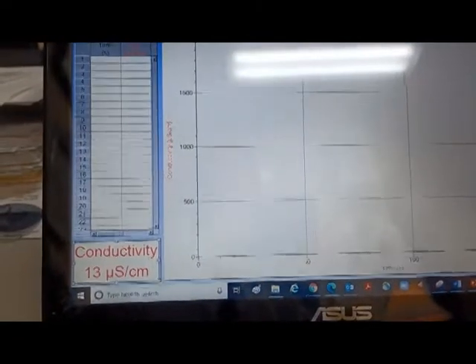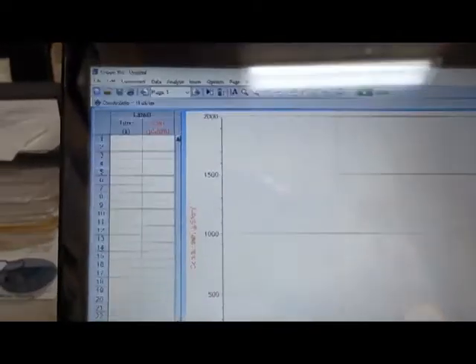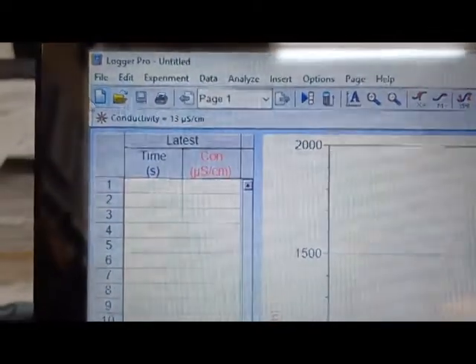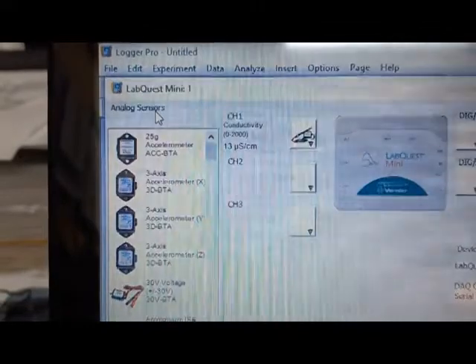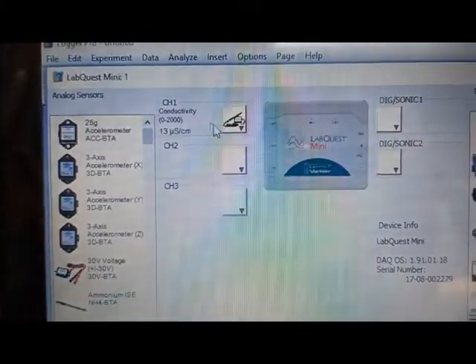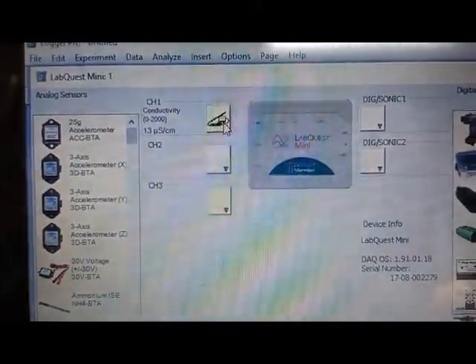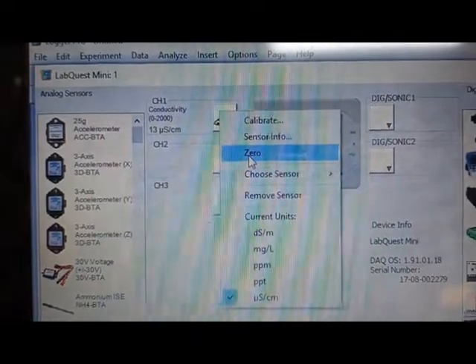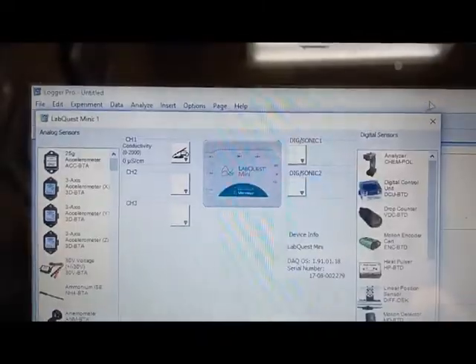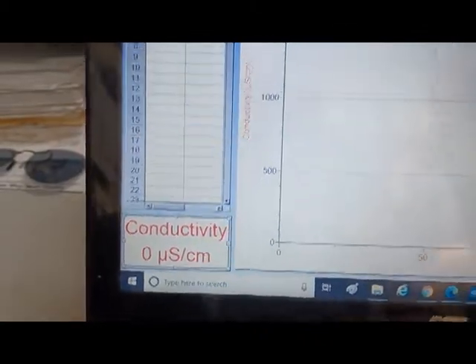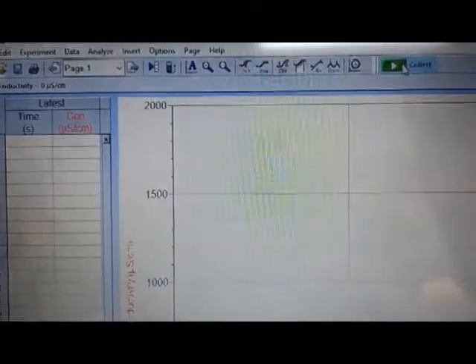Next, you're going to go into your Logger Pro and we're going to zero the probe because it's reading a small value right now. We got to start at 0 in the DI water. You click under the probe, you click here, and you click 0. Then you exit that screen and you can see the conductivity is reading 0. Remember to hit the green button, play, start collecting data.